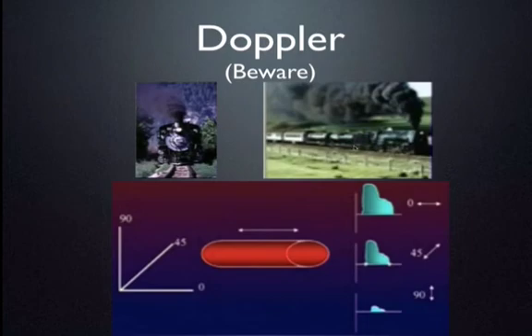Compare that to this angle here. Let's say this is approximately at 45 degree angle to the train that is passing by, and you can see that our velocity is measured to be slightly lower. That's because there is error introduced into your calculation because you're 45 degrees to the train, even though the train in both cases is going the same speed. Well, the same applies to your blood vessel. The closer to zero degrees, i.e. looking straight down the barrel of your vessel, the more accurate you will be.